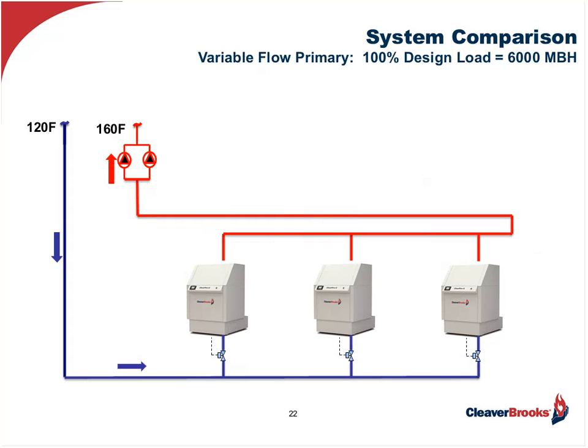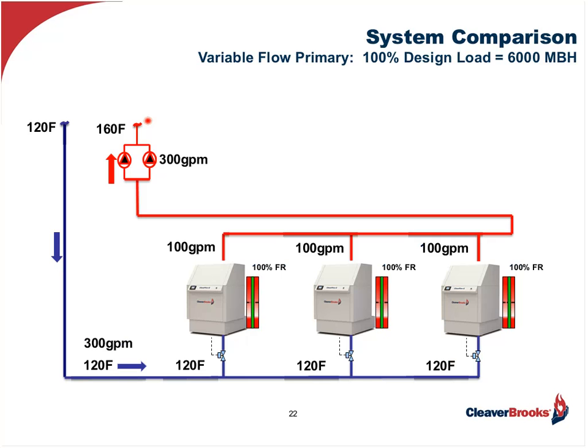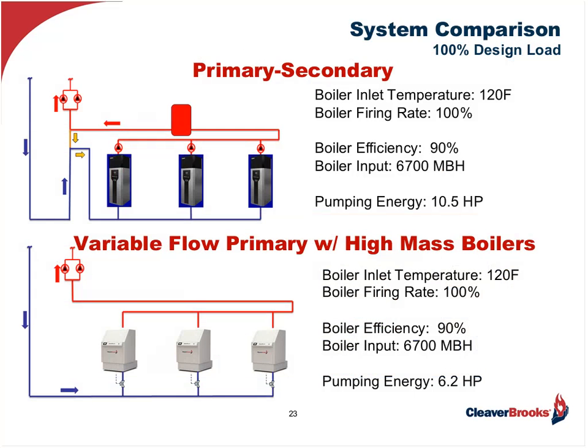Now let's assume we have the same conditions with the variable flow primary. 160 out, 120 in. That'll give us 300 GPM just like before. 120 coming back, which means the boilers are going to see 120. All the isolation valves will be wide open. And as I said, the boilers will see 120. And the firing rate's going to be at 100%. So when you compare the two, you'll see there really isn't any difference at an idealized full load operation.